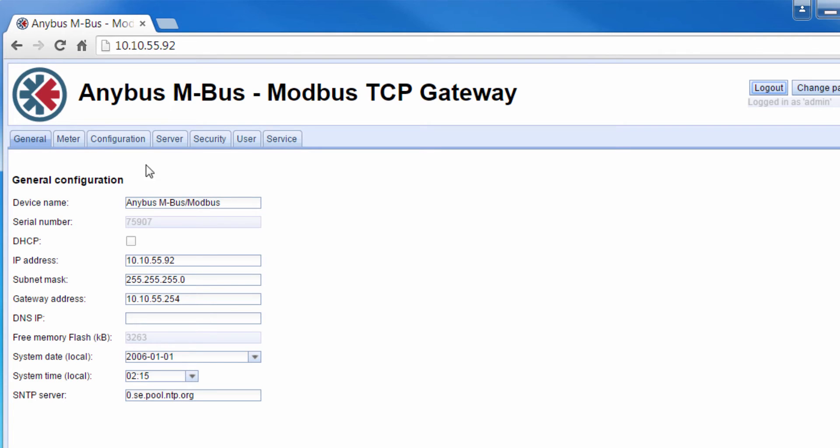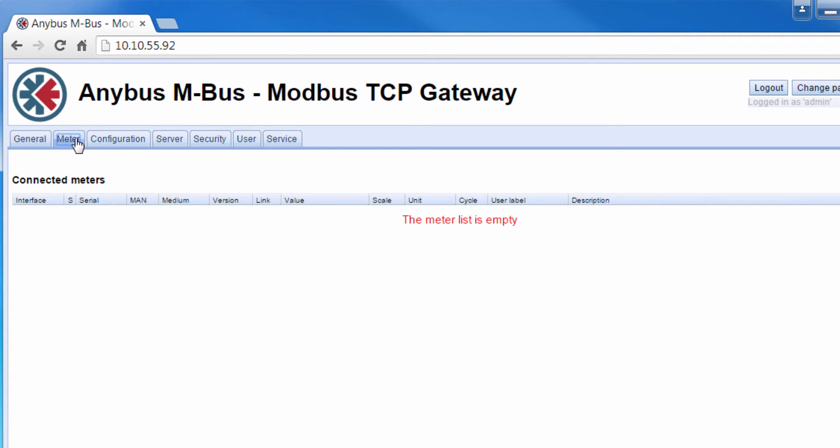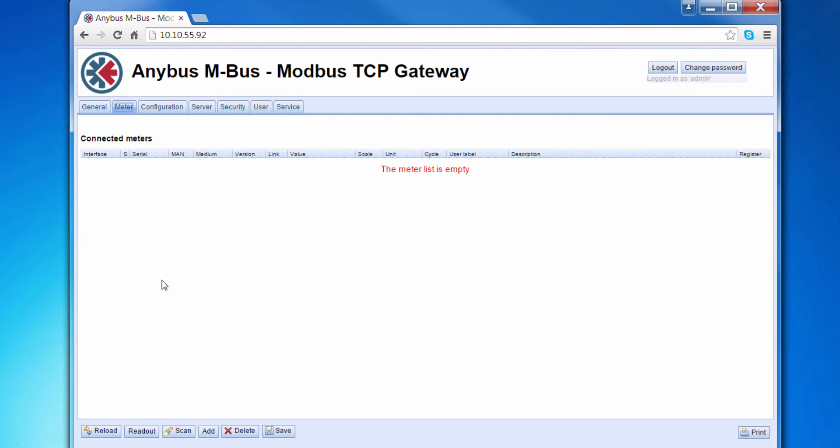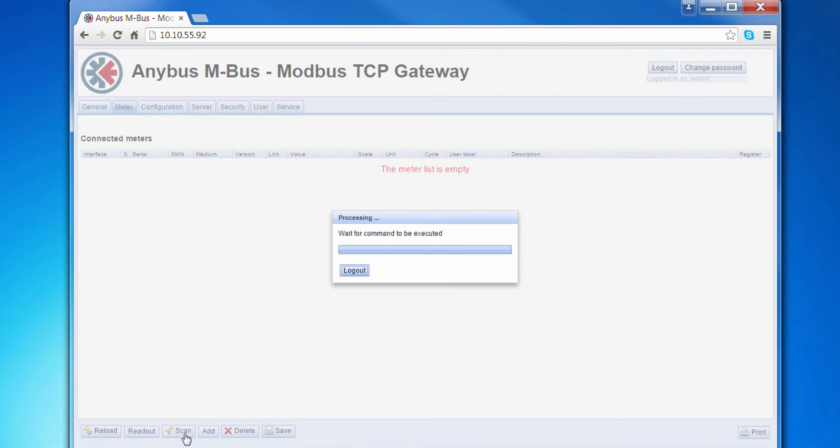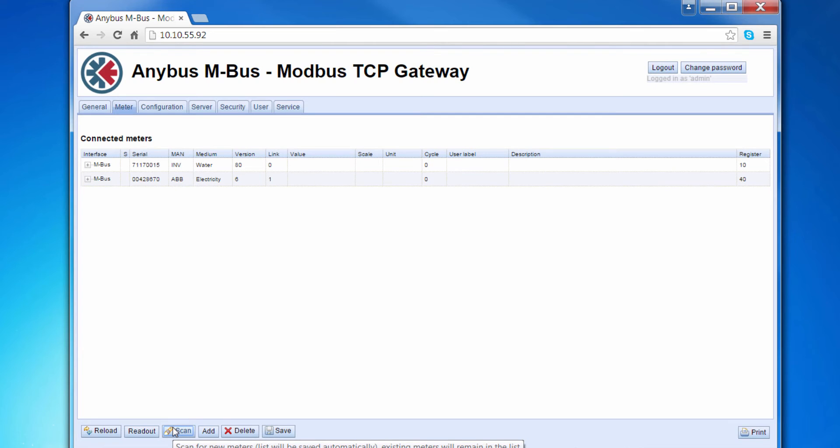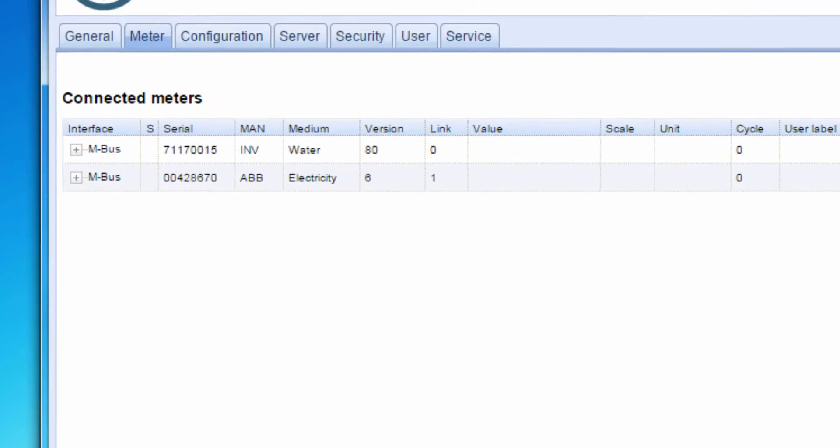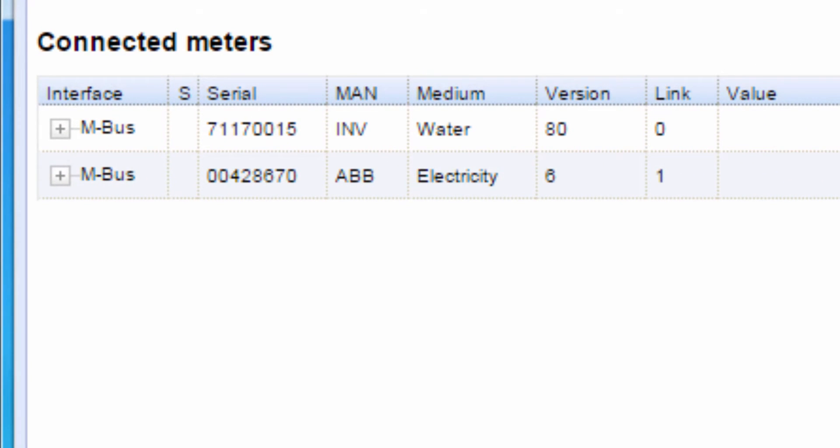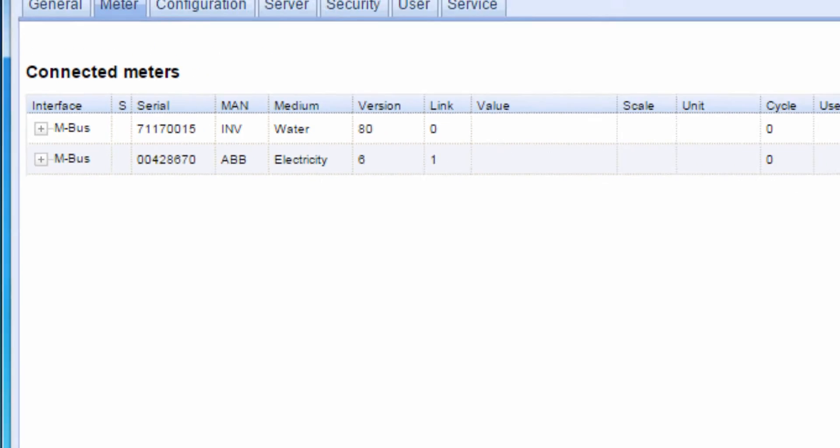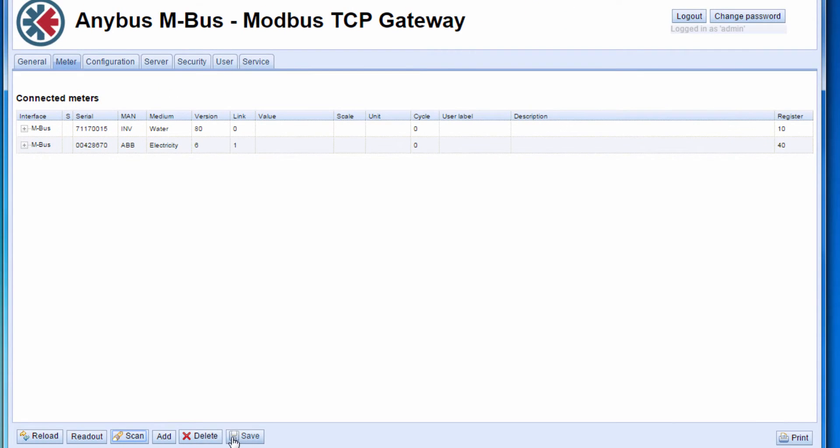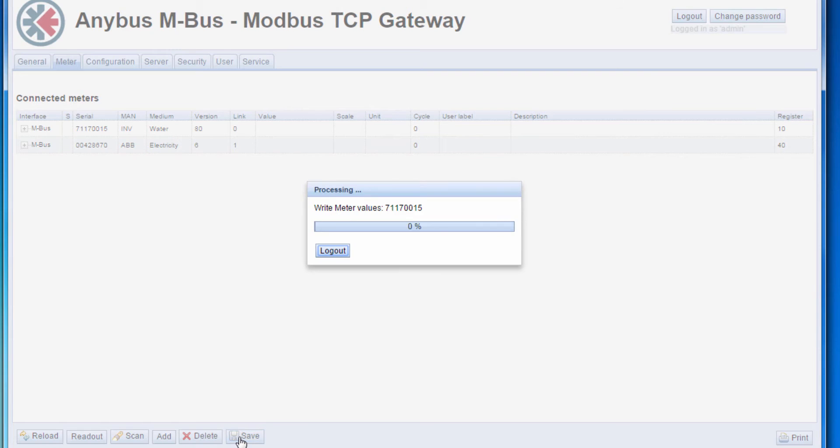Let's have a look under the Meter tab, where we will see all the values from my connected devices. I click Scan and the gateway starts looking for MBUS devices which are connected to the network. I can now see that the gateway has found two MBUS devices: the water meter from Sensus and the electricity meter from ABB. I click Save to save these sensors.